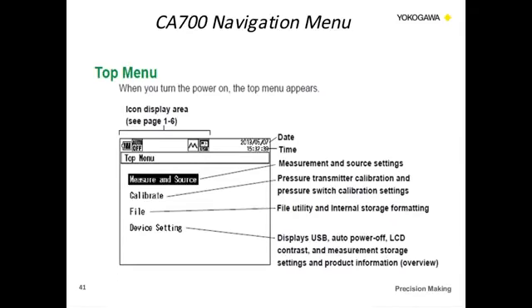So when we get to the unit, this is the main screen that you would use to navigate the different functions for the CA700. The first screen is the measurement source, so this will provide an instantaneous reading of pressure and also for milliamps, and that can be changed to different values. The calibrate function, this is where you would do your as found, as left. The file feature, so this will give you an idea in terms of where all the files that you save are. You can go in there and you can delete files as well. The device settings, this is where you would change the contrast, the auto off. This is where you can also turn on and off the 250 ohm resistance as well.